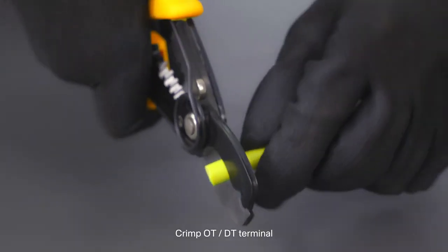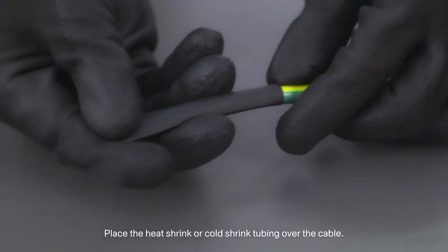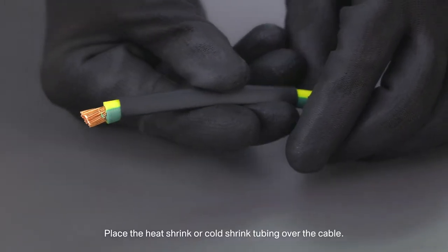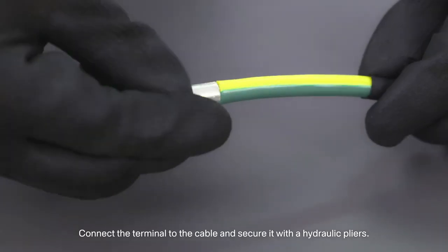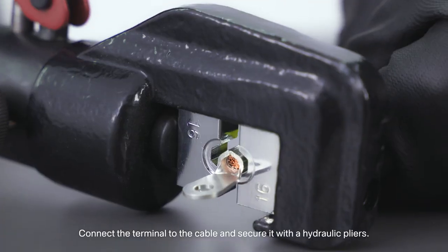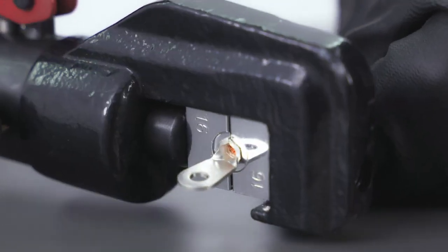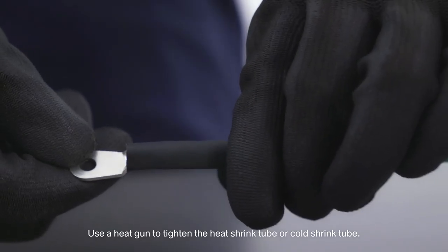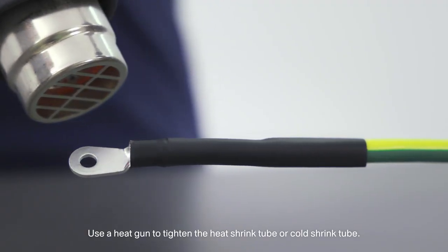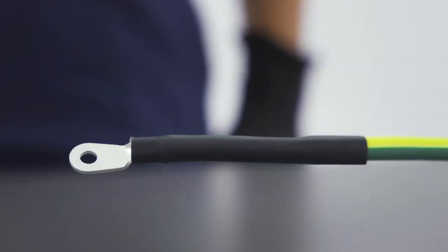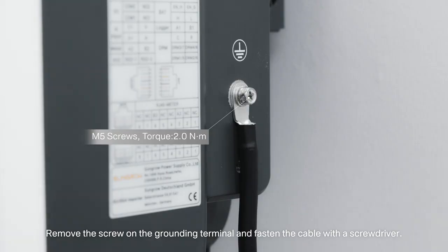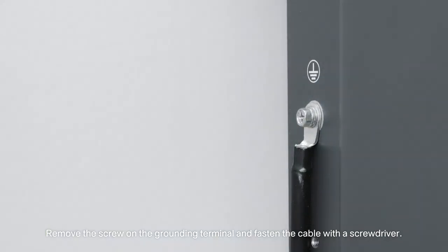Crimp OT/DT terminal. Place the heat shrink or cold shrink tubing over the cable. Connect the terminal to the cable and secure it with a hydraulic pliers. Use a heat gun to tighten the heat shrink tube or cold shrink tube. Remove the screw on the grounding terminal and fasten the cable with a screwdriver.